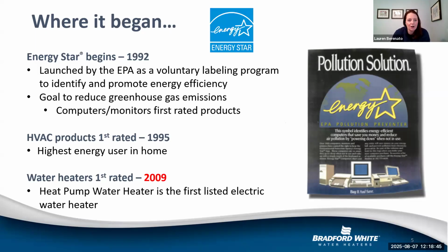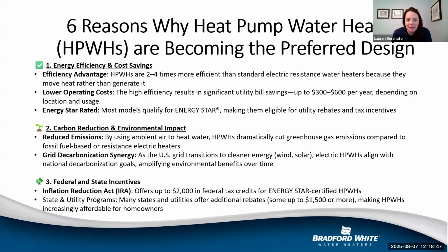So what exactly are reasons why heat pumps became the preferred design? How did this really even come to be? One of the things that really came into play was the energy efficiency as well as cost savings. Heat pump water heaters are 2 to 4 times more efficient than your standard electric resistance water heaters because they move heat rather than generate heat. They have that lower operating cost because of that high efficiency. So it can typically have savings of anywhere from $300 to $500 or $300 to $600 a year, depending on usage.